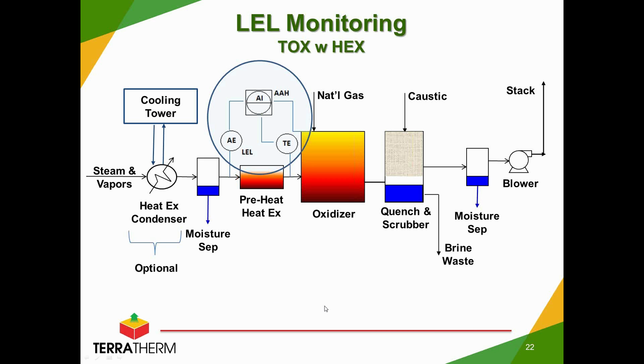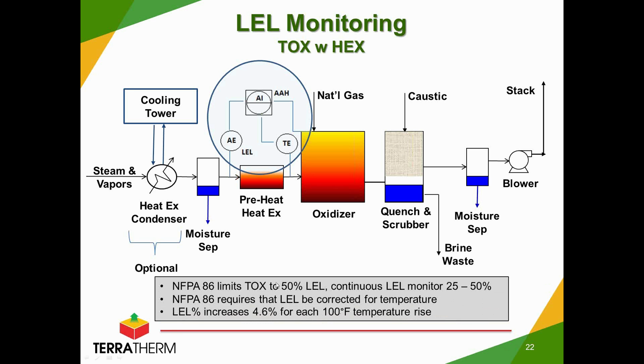One thing to consider when you're talking about approaching the operational limits of an oxidizer, you need to be careful about the LEL level. Any thermal oxidizer that's governed under NFPA 86, NFPA 86 will tell you that you can operate an oxidizer up to about 50% of the LEL, provided that you've got continuous LEL monitoring anytime you expect to exceed 25% of the LEL.